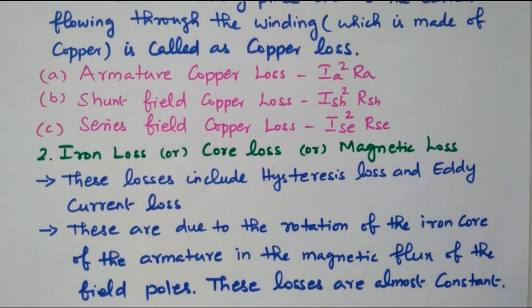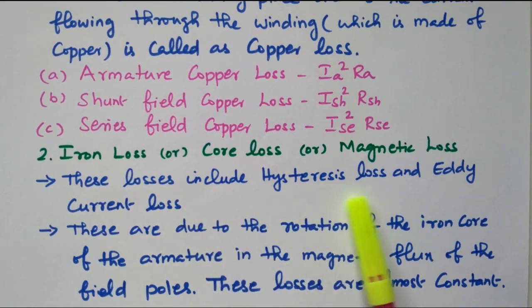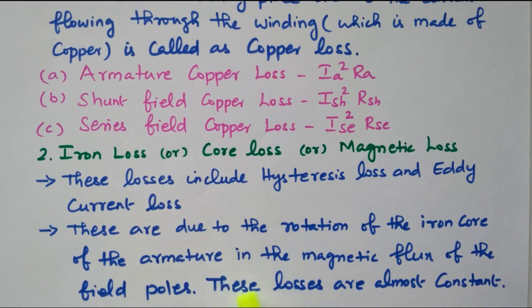Field may be series field or shunt field. Then iron loss, core loss, or magnetic loss. The losses include the hysteresis loss and eddy current loss. These losses are due to the rotation of the iron core, because of that it is called iron loss or core loss. Iron core of the armature rotates in the magnetic flux of the field poles. These losses are almost constant.